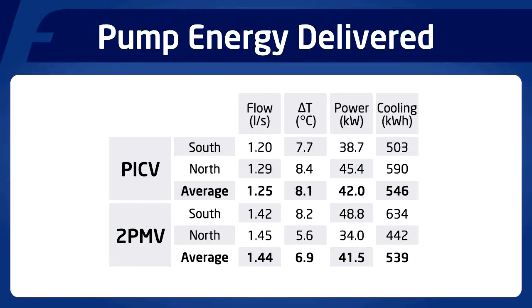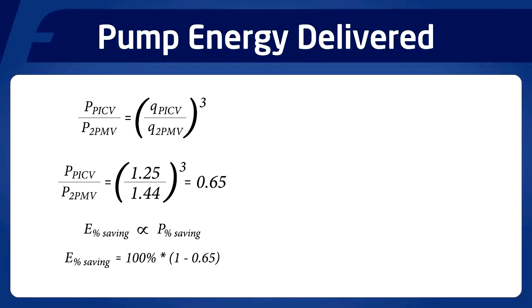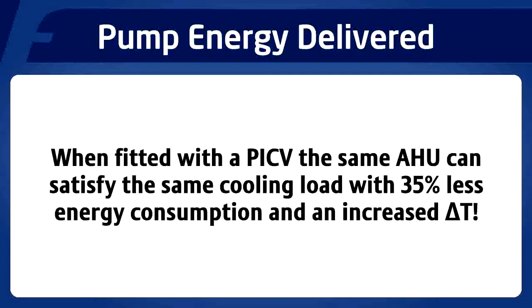The table shows the recorded average flow rates and water delta T's together with the calculated average pump power and daily cooling load delivered when air handling units are fitted with the pressure independent control valve and the two-port modulating valve. We can see that when averaged out, the same cooling load of 540 kilowatt hours is achieved at lower flow and higher delta T when the air handling unit is fitted with a pressure independent control valve. We can use our pump affinity laws to calculate the energy saving achieved due to the fitting of the pressure independent control valve. Finally, we can summarise our findings that when fitted with a pressure independent control valve, the same air handling unit can satisfy the same cooling load with 35% less pump energy consumption and an increased delta T.